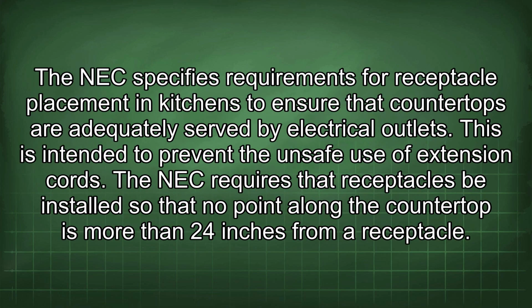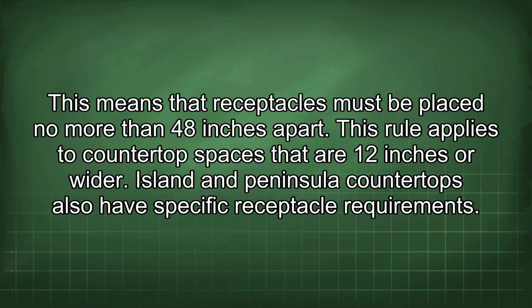The NEC specifies requirements for receptacle placement in kitchens to ensure that countertops are adequately served by electrical outlets. This is intended to prevent the unsafe use of extension cords. The NEC requires that receptacles be installed so that no point along the countertop is more than 24 inches from a receptacle. This means that receptacles must be placed no more than 48 inches apart. This rule applies to countertop spaces that are 12 inches or wider.